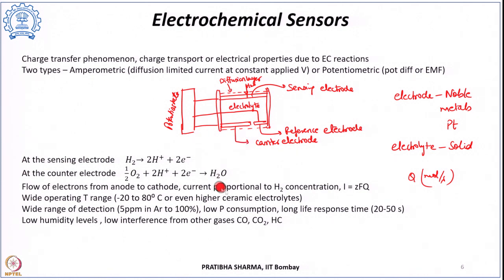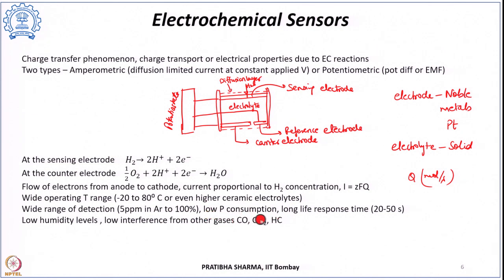The measured current is calibrated to determine hydrogen concentration. These sensors have a wide operating temperature range from −20°C to 80°C, with care needed to prevent the electrolyte from freezing. Even higher temperature ranges can be achieved using ceramic electrolytes. Detection range extends from 5 ppm in argon to 100%, with very low power consumption, though response time tends to be somewhat longer.